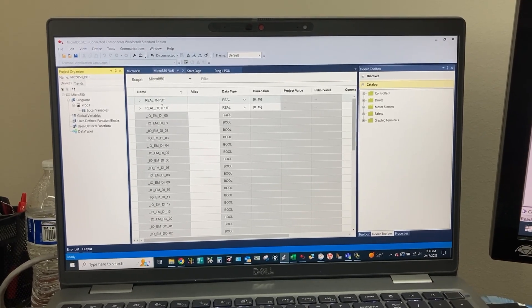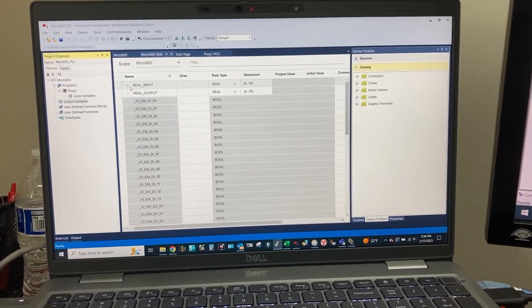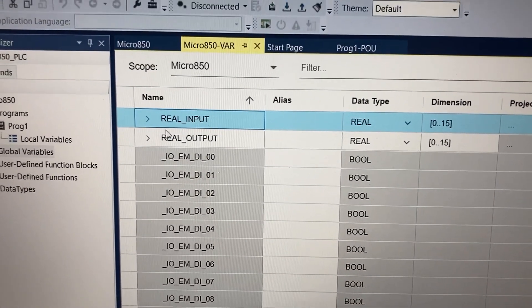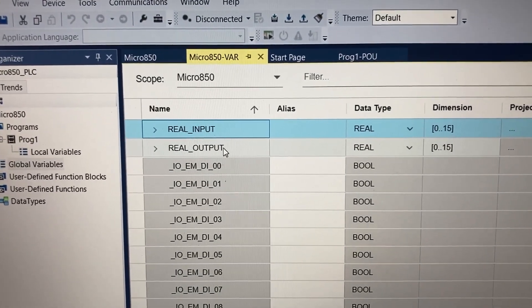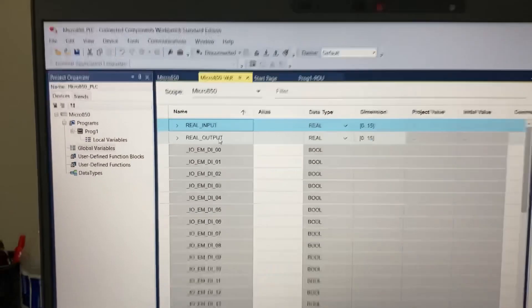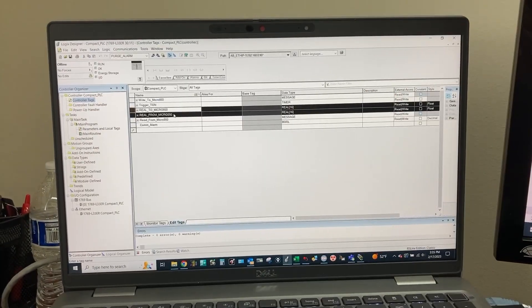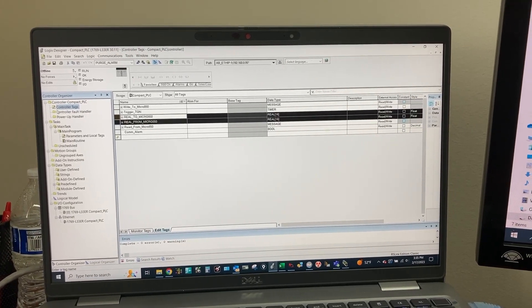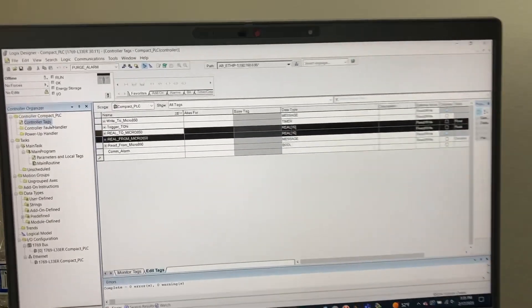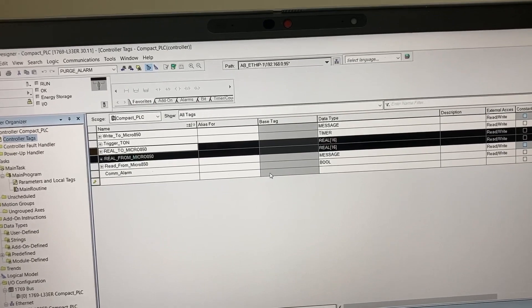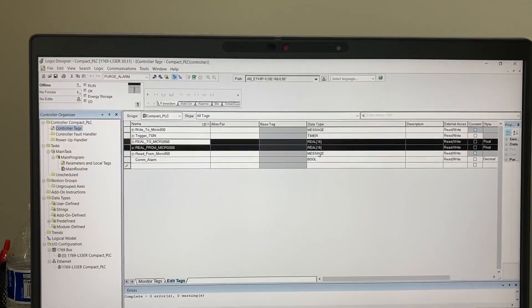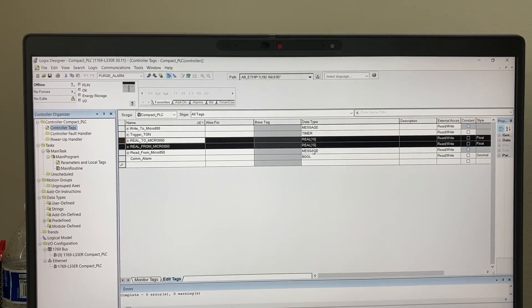So the CompactLogix PLC will need to send data to Real Input, and it will need to collect data from Real Output from the Micro 850 PLC. For the CompactLogix PLC programming under controller tags in Studio 5000 Logix Designer, we will have two tag arrays of 16 elements for data it sends to and collects from the Micro 850 PLC.